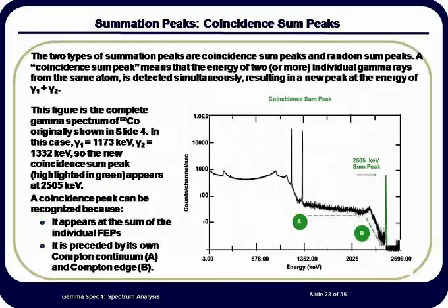A coincidence sum peak occurs when a radionuclide has two energy levels that decay from one to the next state in rapid succession. For reasons beyond the scope of this tutorial, it is possible that both the gamma rays strike the detector simultaneously, making it appear to the detector as a single event and recording the energy as the sum of the two gamma rays.